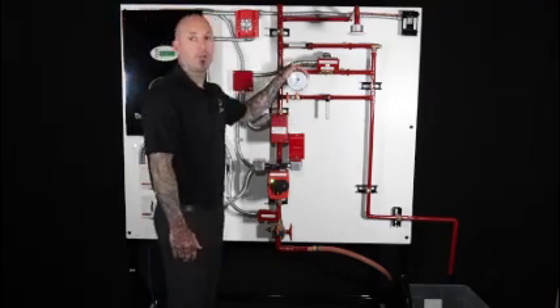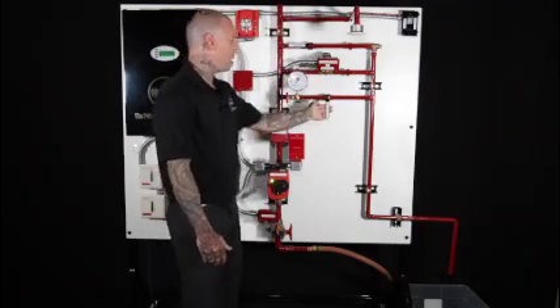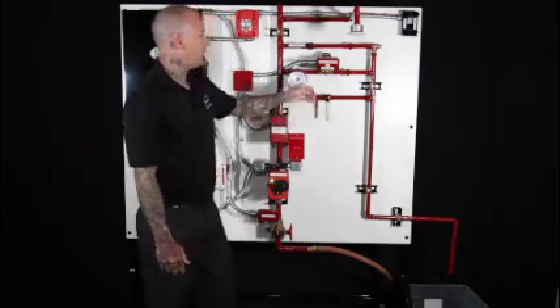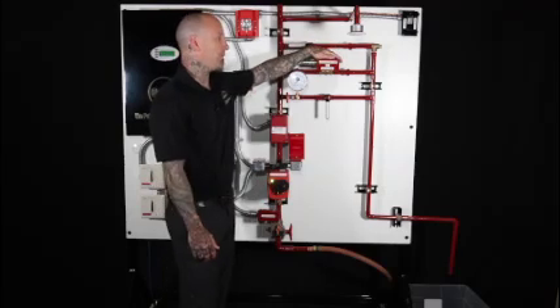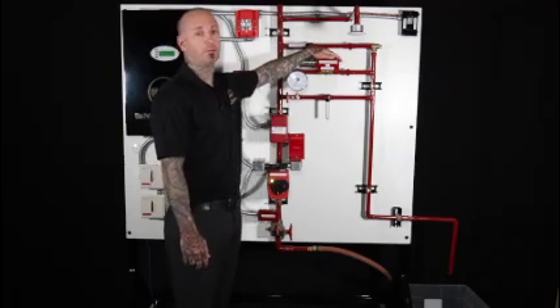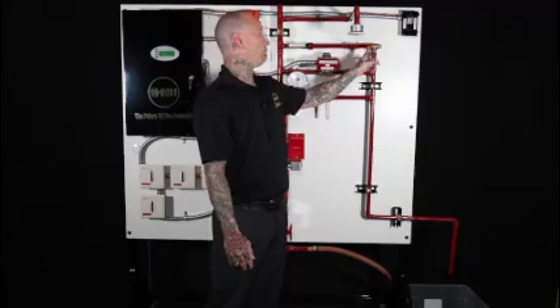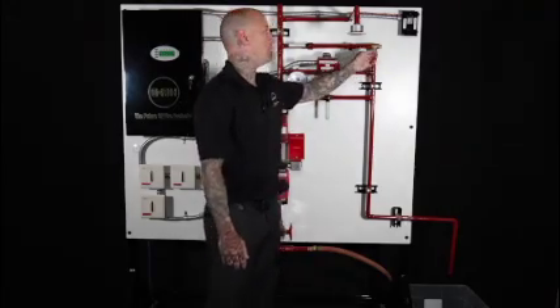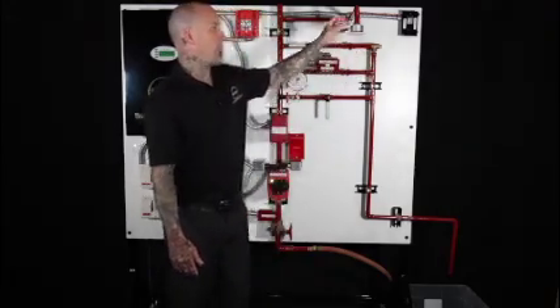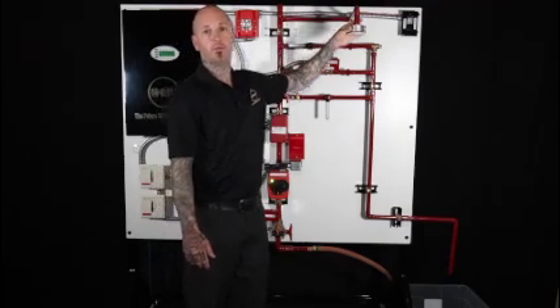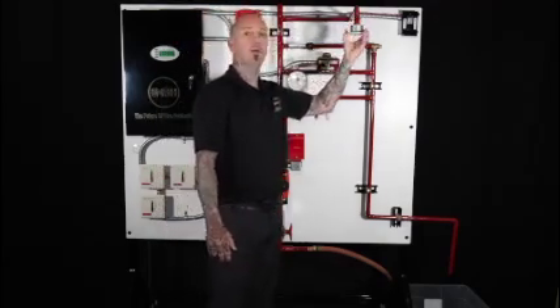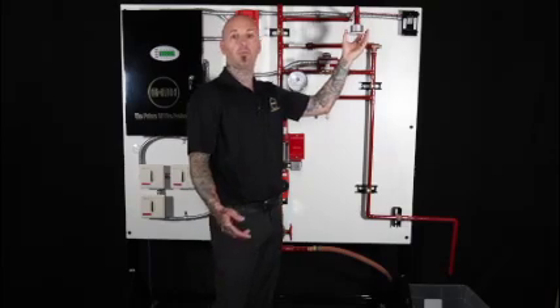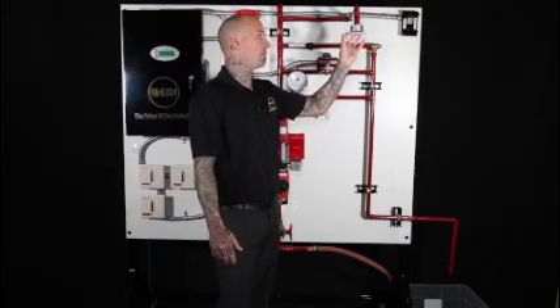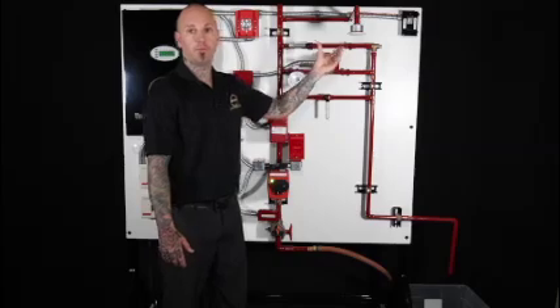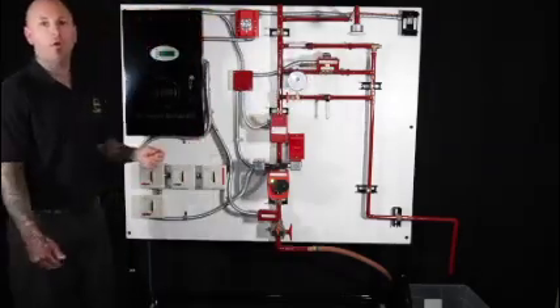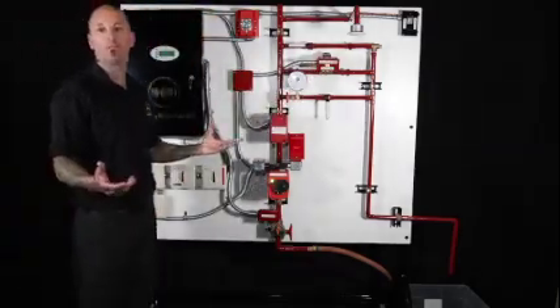Here's a water pressure gauge and our main drain valve. Above that is a solenoid release valve for the auxiliary drain line. Then you have your pressure relief valve, and here's the proposed electronically monitored fire sprinkler head. Now this head is not an actual head wired to operate at this time and only used right now for display purposes so that we can see everything, how it works without spraying water.